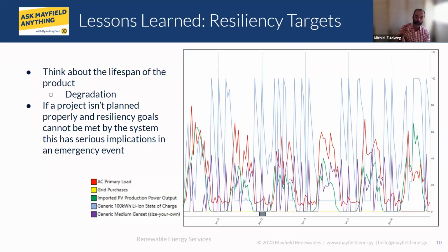But if you see on June 13th in the middle, the batteries are charging and discharging about 6 times at a pretty heavy and aggressive charge-discharge rate. Just because of that heavy charging and discharging, that's going to reduce the lifespan of those batteries. And even if you're at a 1C discharge rate, you've got to check the warranty of the battery to make sure the asterisk they put on that warranty means you can still actually do that. Does it reduce the total life cycle? And then will it still be able to meet that target at year 15?